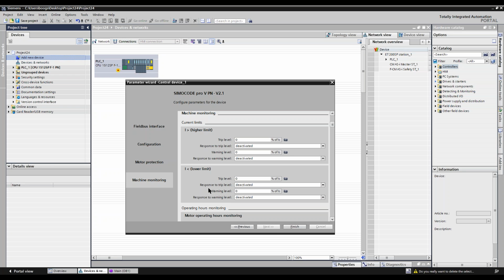Everything's going great. Well, in the PLC, you could have a high and a high-high and a low and a low-low. Meaning, at high, my pressure's jumped up 10 psi, so I'm up to 60. So it's still okay. It's within the normal nominal process set points, but it's getting kind of high, something the operator needs to keep an eye on. But if it goes past the high, then there's something going wrong. Now we're getting up into 70, 80 psi. The flanges are not rated for that, or the hoses are not rated for that. That's where the operator says, whoa, we've got a problem, let's maybe shut this off, or let's call somebody and ask, hey, what's going on? And that's where you set those into the PLC.